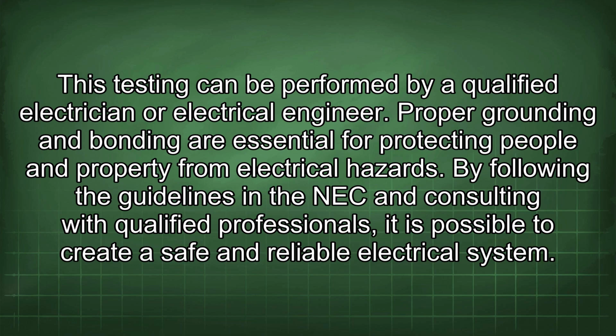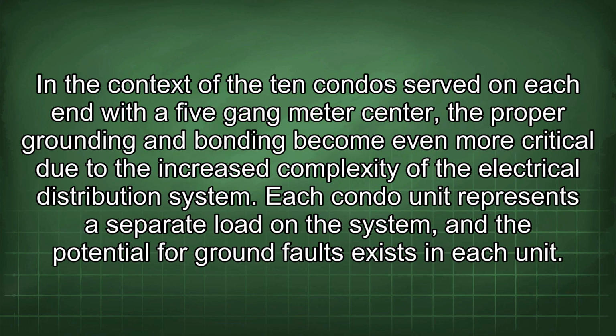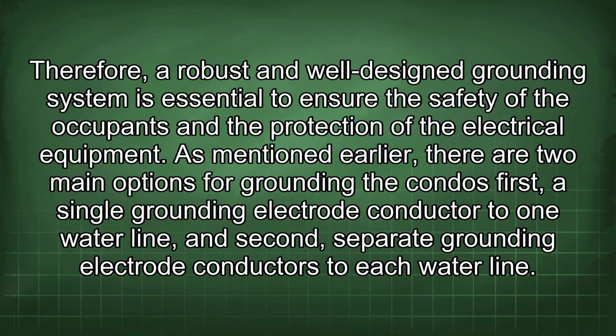By following the guidelines in the NEC and consulting with qualified professionals, it is possible to create a safe and reliable electrical system. In the context of the 10 condos served on each end with a 5-gang meter center, the proper grounding and bonding become even more critical due to the increased complexity of the electrical distribution system. Each condo unit represents a separate load in the system, and the potential for ground faults exists in each unit. Therefore, a robust and well-designed grounding system is essential to ensure the safety of the occupants and the protection of the electrical equipment.